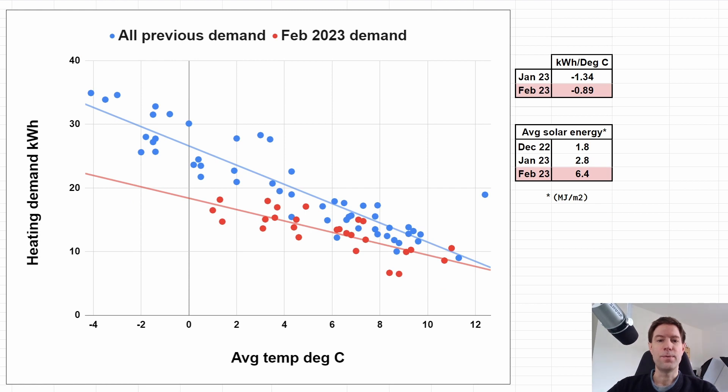This is the chart of heating demand in kilowatt hours versus the average temperature for each day during February — shown as red dots — compared to all of the previous data from December and January in the blue dots. You can see that generally speaking the February dots lie below the December and January dots by quite a significant margin. The slope of the best fit line through the February data is minus 0.89 kilowatt hours per degree, meaning for every degree colder it gets we use 0.89 kilowatt hours extra for heating. Comparing that against the January value of minus 1.34 kilowatt hours per degree, you can see that the blue line is quite a lot steeper.